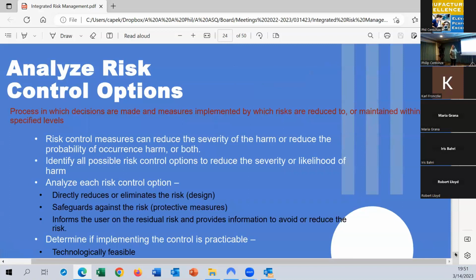When we're looking at risk controls, if you've ever been in a brainstorming session for how we can reduce this risk, people will think of all kinds of things, right? At the end of the day, you have to ask, is this control worth it? Sometimes controls, especially alarms, can be a worse thing because of alarm fatigue. If you have too many alarms in your instrument, the operators stop paying attention to the alarms, so it's like doing nothing. If you put in too many components, it might become a reliability issue because now you have more parts that can fail. So you really have to evaluate all the potential controls and pick the ones that are most effective at mitigating. So once we look at risk control measures and say these are the ones we're going to implement, then we can re-estimate the risk, assuming the control measures are implemented appropriately.